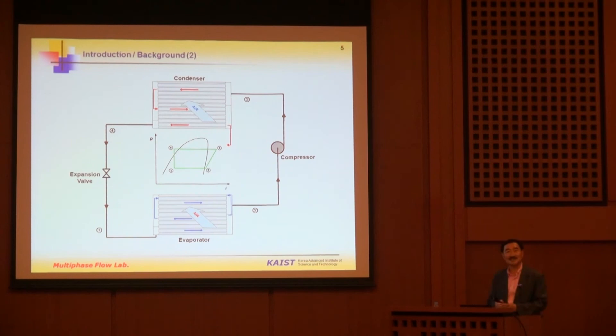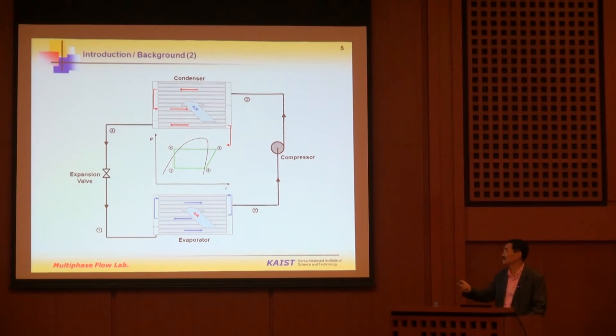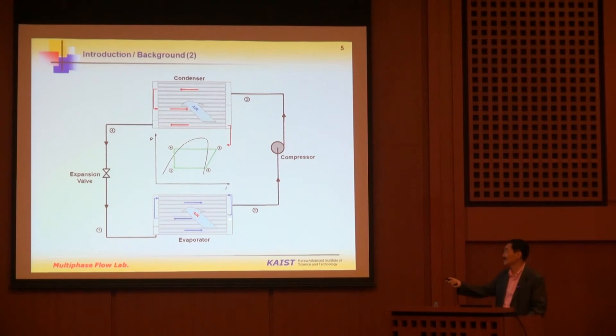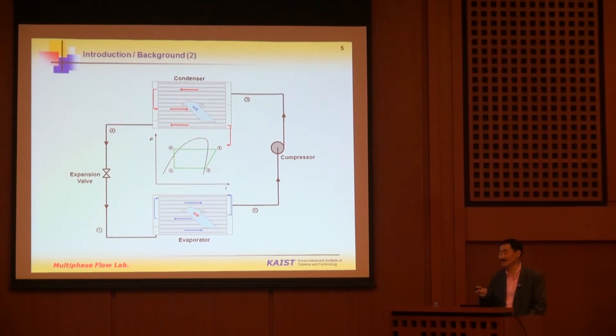Here is a typical refrigeration cycle in a pressure-enthalpy diagram with saturation curve and points one, two, three, and four. Between points one and two you have the evaporator. A two-phase mixture comes out from the expansion valve, is introduced to the header, and distributed into parallel channels, then through an intermediate header into another set of parallel channels. The mixture is converted into vapor — saturated or superheated — then goes through the compressor.